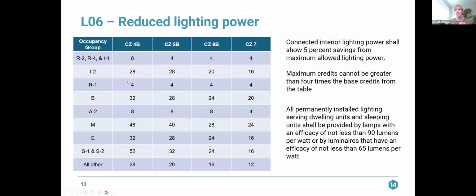So you'll see in offices, they're going to be weighting this very heavily. In schools, they're going to be weighting this very heavily. Groups R2, R4, and I1, we're just looking at the common area spaces here, right? I2, they're also going to be weighting this fairly heavily. Oh, I'm sorry. And then to achieve credits here for residential occupancies, all permanently installed lighting serving dwelling units and sleeping units shall be provided with lamps with an efficacy of not less than 90 lumens per watt or by luminaires that have an efficacy of not less than 65 lumens per watt. So there are requirements for the fixtures within the residential units themselves as well. And this is, again, the maximum number of credits you can receive in each climate zone for your occupancy type.